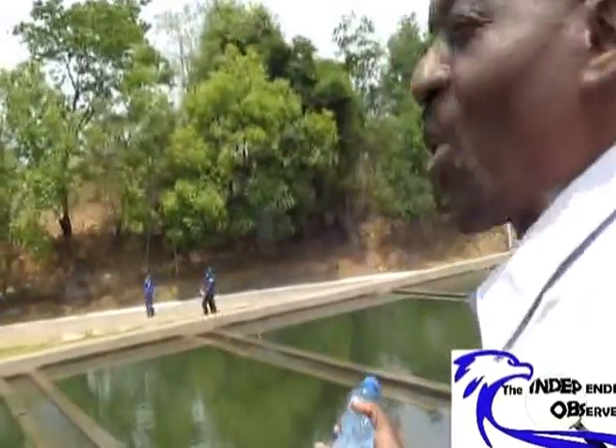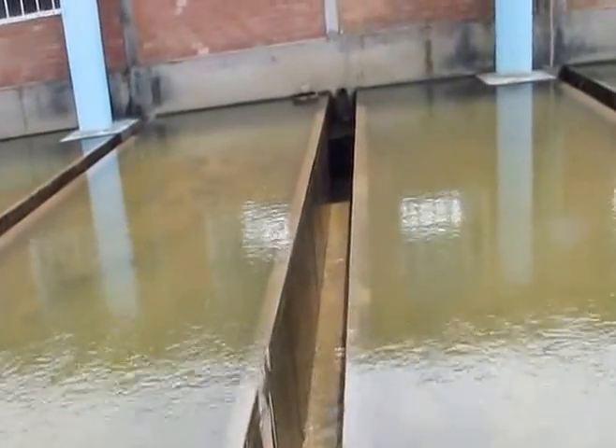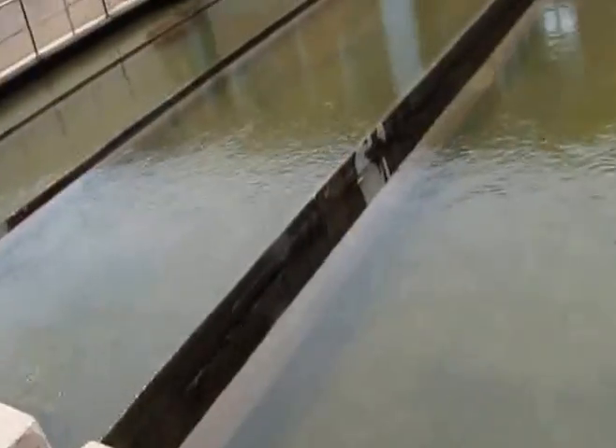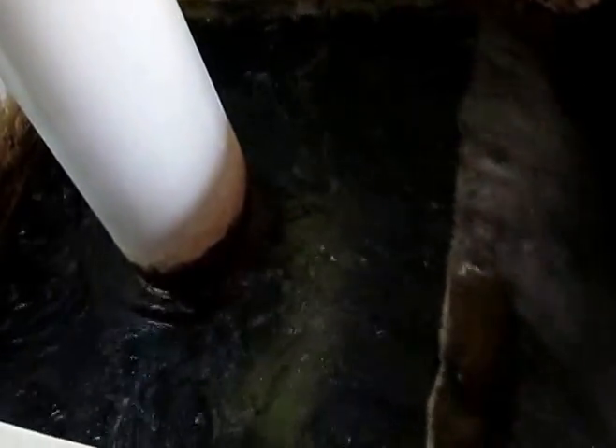pre-chlorination. So all the suspended particles have to settle down into here to form a sludge blanket which is collected at the bottom down there. So much that clear water will rise at the top, because the raw water transmission from the premixer is down at the bottom here, and the clear water will rise on top. Then these launders which you are seeing on top of this clarifier are the ones which are responsible to carry over to the filters clarified water, or that water which has been separated.